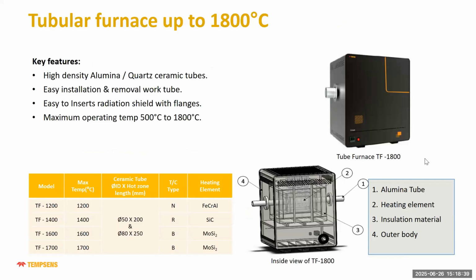Now the tubular furnace, up to 1800 degrees centigrade. If a customer requires a furnace with a tube, the advantage is that a small material can be heated at high temperatures under vacuum or any atmospheric condition, using special types of tubes. For 1800 degrees centigrade, we can give an alumina tube of 99.7%, and for 1200 degrees centigrade, quartz or metal tubes. It is easy to install and remove, and easy to insert a radiation shield. We can use flanges on both sides, with operating temperature from 500 degrees centigrade to 1800 degrees centigrade.